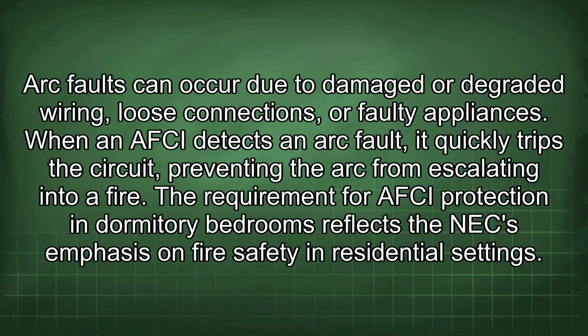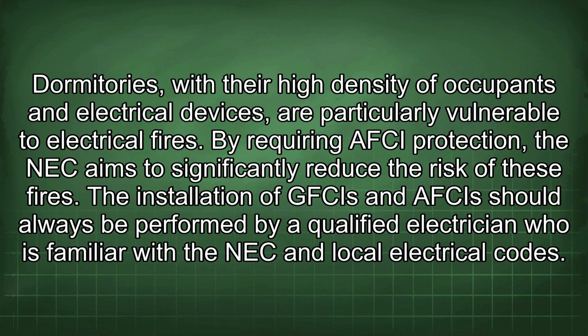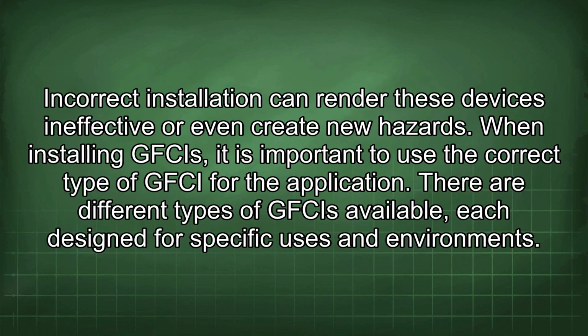The requirement for AFCI protection in dormitory bedrooms reflects the NEC emphasis on fire safety in residential settings. Dormitories, with their high density of occupants and electrical devices, are particularly vulnerable to electrical fires. By requiring AFCI protection, the NEC aims to significantly reduce the risk of these fires. The installation of GFCIs and AFCIs should always be performed by a qualified electrician who is familiar with the NEC and local electrical codes. Incorrect installation can render these devices ineffective or even create new hazards.